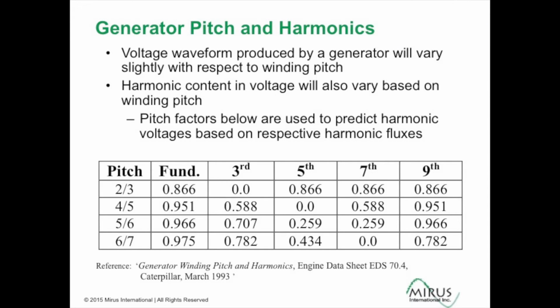The table on this slide shows the relationship between a generator's winding pitch and the harmonic voltage distortion that it will produce. The pitch factors shown indicate the relative level of distortion at each harmonic. So if we look at the 2/3 pitch generator, we'll see that there's zero introduction of third harmonic in theory.